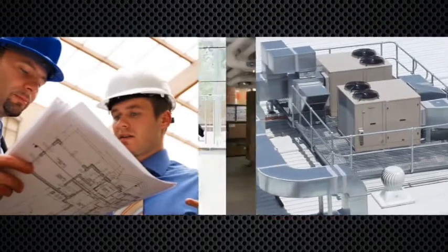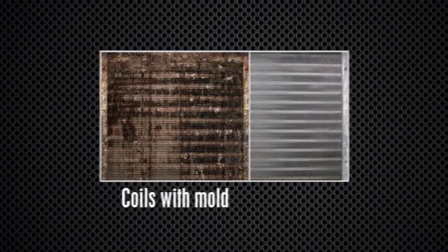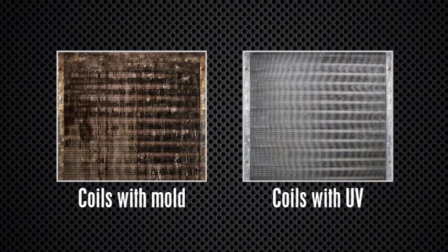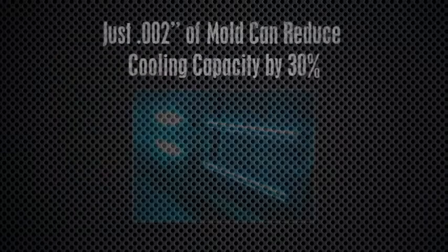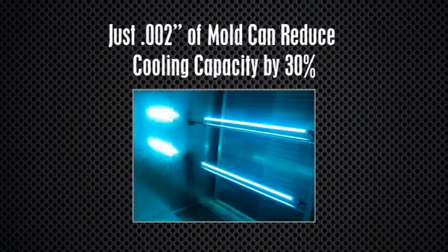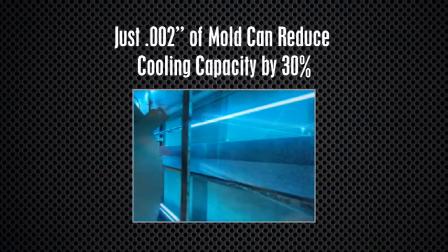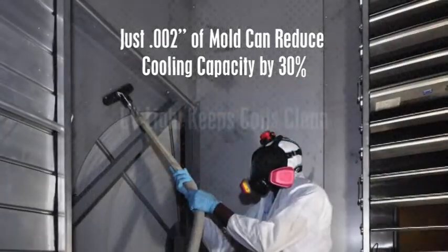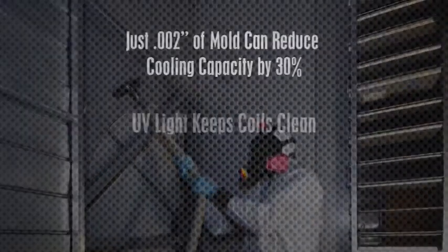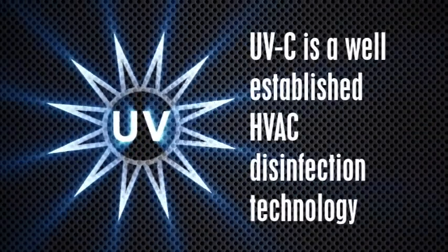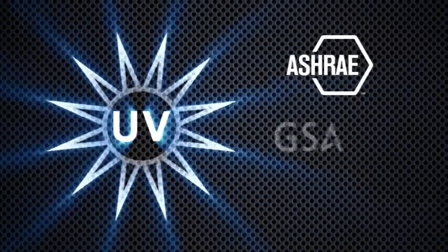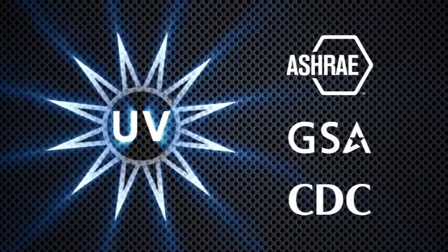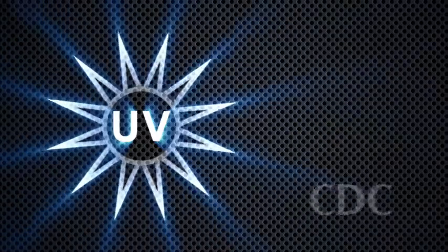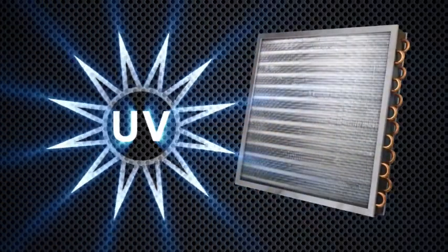Fresh Air UV systems remove 99.9% of microbial growth on cooling coils, which directly impacts air system maintenance and efficiency. Studies show a layer of mold only 0.002 inches thick can reduce cooling capacity by as much as 30% and usually requires a costly chemical-based cleaning procedure. UVC is a well-established HVAC disinfection technology. ASHRAE, USGSA, and the CDC all recognize its effectiveness. It's a fact. UVC light keeps coils clean.